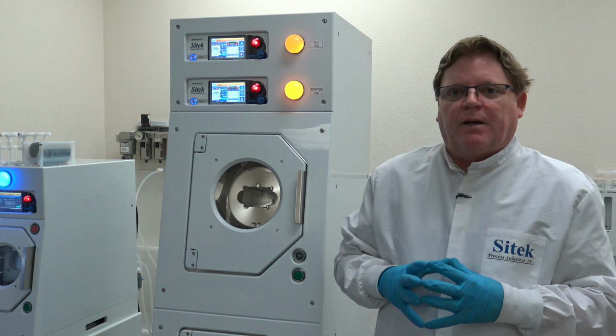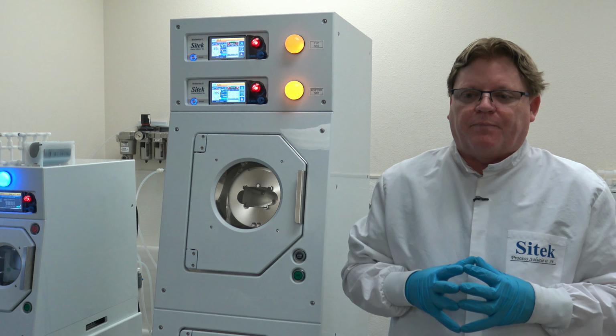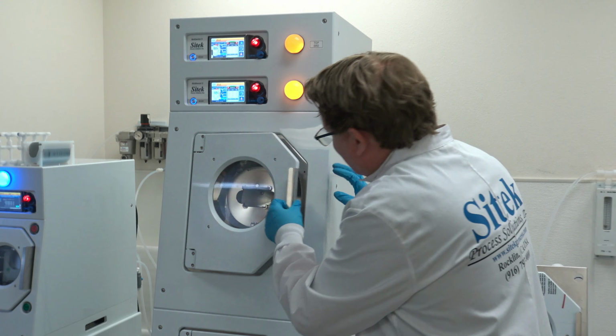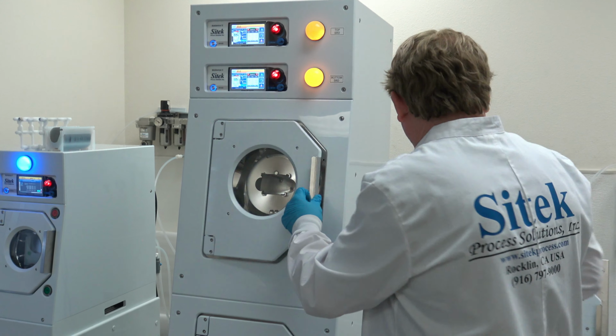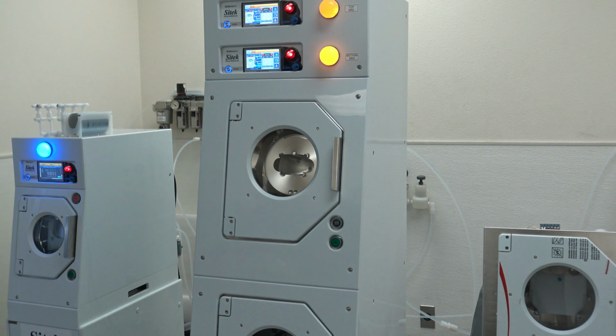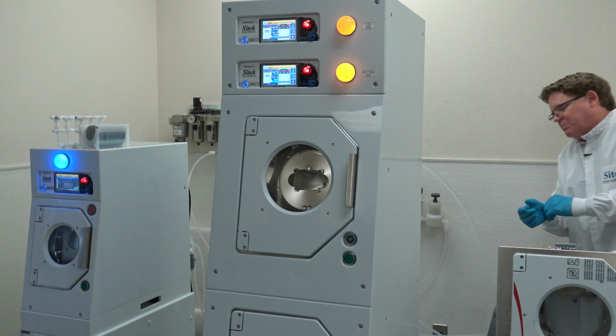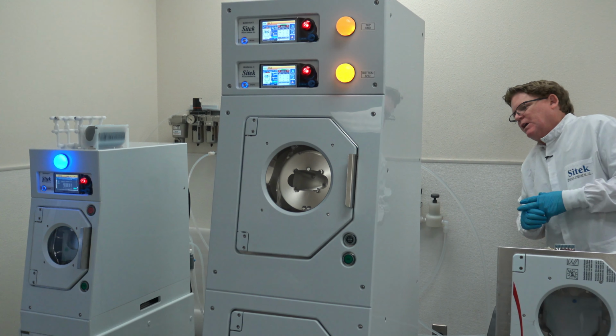This system has 3 of the traditional options that are offered. One is the anti-static module, I see the probes right there. Number 2 and 3 are going to be the water recirculation option, I see that here, and the DI resistivity.